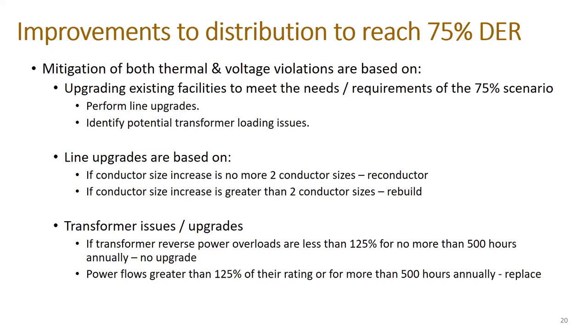So we looked at either performing line upgrades as necessary to mitigate those violations or potentially upgrading substation transformers. And when we looked at the mitigation, rather than doing this incrementally for 25%, 50%, and 75%, because this is going to be a relatively large infrastructure investment, we said, okay, if we're going to make the investment, we're going to do whatever is necessary to ultimately reach a 75% DER penetration level. So we didn't do the incremental steps along the way. We ultimately just said, if we're going to upgrade it, we're going to upgrade it to meet the requirements of the 75% penetration level.